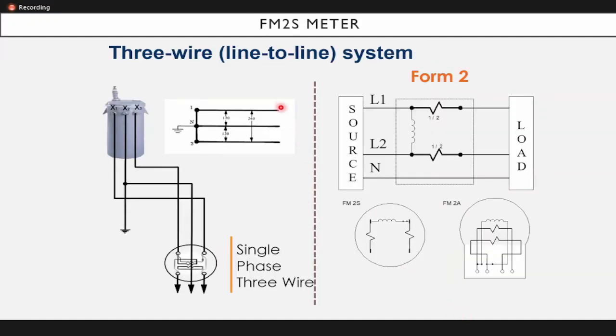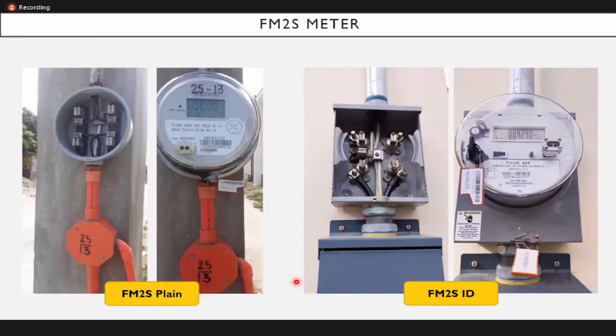Now, this is the three-wire line-to-line system, and normally and typically, form 2S. So, kanina po, pag line-to-ground, 1S. Pag line-to-line, 2S. Okay? So, this is a typical 2S connection. This is a plain meter. As I've said, the upper part is the line side, the lower part is the load side. For this one, this is the ID meter or the indicating demand meter, form 2S.